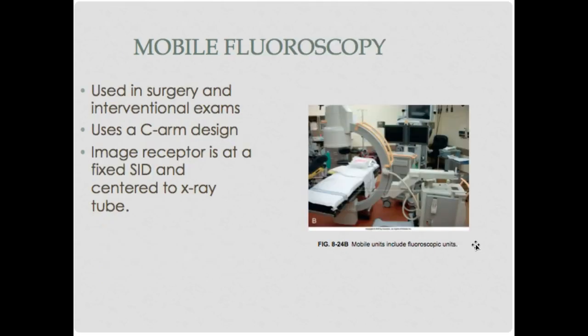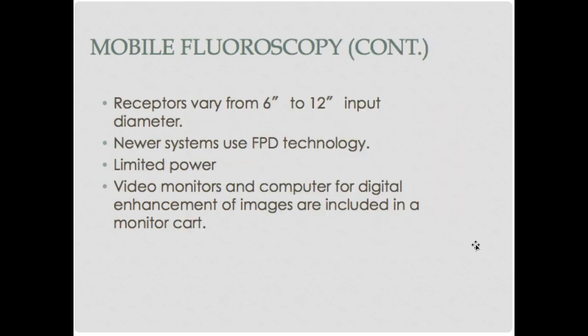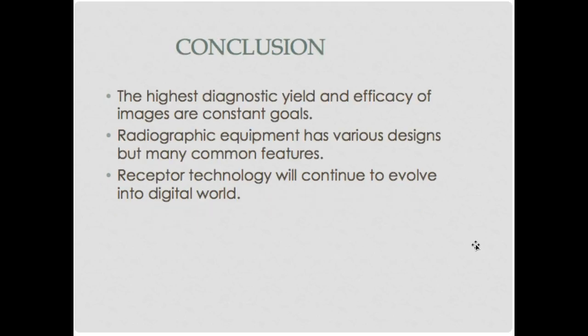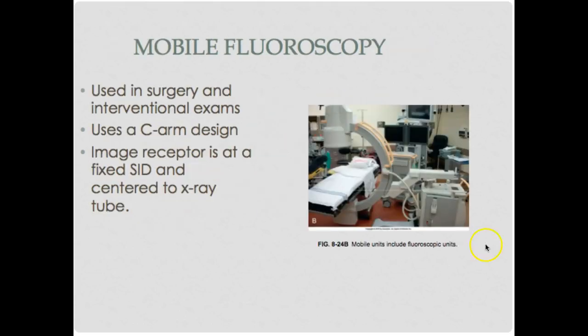C-arms are used in fluoro and interventional procedures. The image receptor and the tube are at a fixed distance — nothing can change that. The receptors vary from 6 to 12 inches in diameter depending on the magnification and detail needed. Newer systems use flat panel detector technology. Video monitors and computers for digital enhancement of images are included in the monitor cart — you always want to turn those toward the doctor so they can see exactly what they're doing.